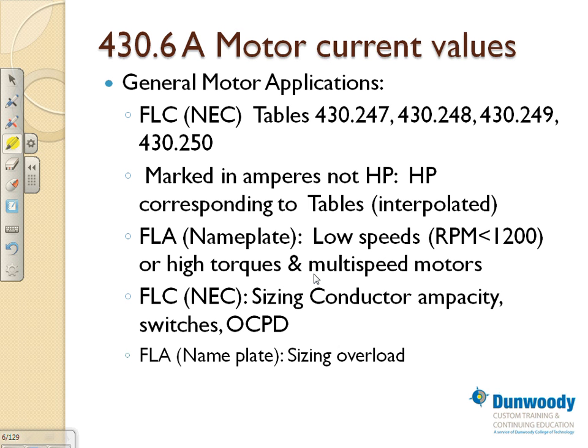Nameplate. Most of the motors that we run, guys, are 1800 RPM synchronous speed, very common motors. 3600 RPM is also a synchronous speed. These are very common equipment that run at 1800 RPM synchronous speed, so 1725 is the RPM that it actually runs at. If you have slow motors that run at less than 1200 RPM, then they don't want you to use the code. They want you to use the full load amp that's printed on the nameplate of this piece of equipment.